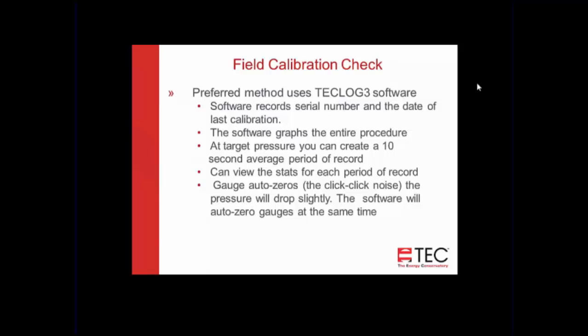Another big advantage is that the gauges will all auto zero at the same time, and there is a slight pressure drop when it auto zeros, and that's one of the big advantages. If you turn on all the gauges at the same time, they'll auto zero at approximately the same time. But if you're playing around with the syringe trying to hit that target pressure and it auto zeros, then you're kind of starting all over and adjusting the pressure again.